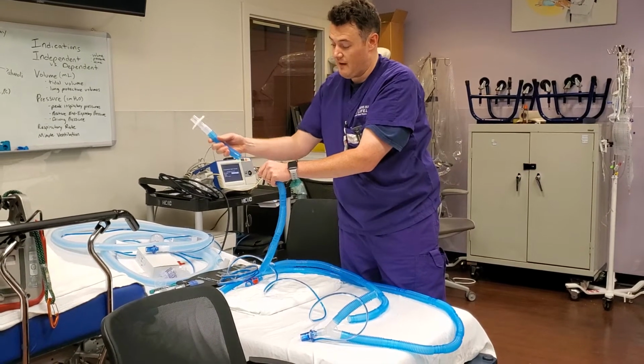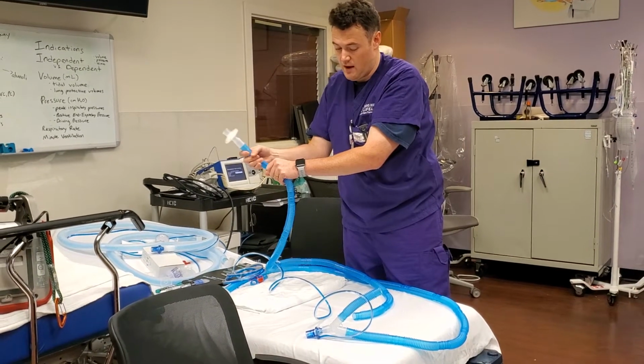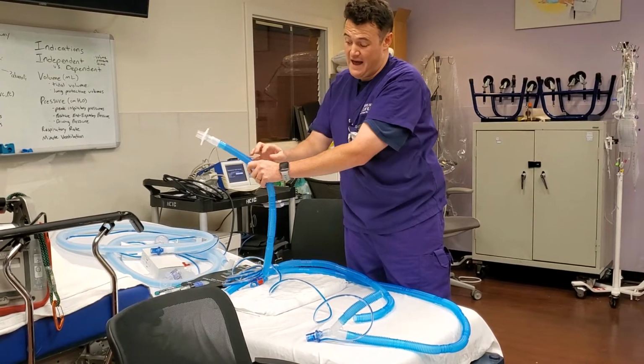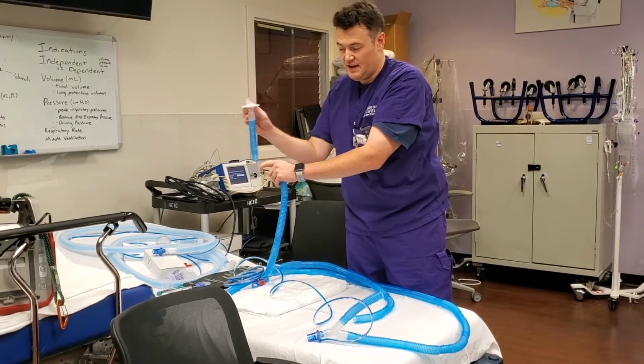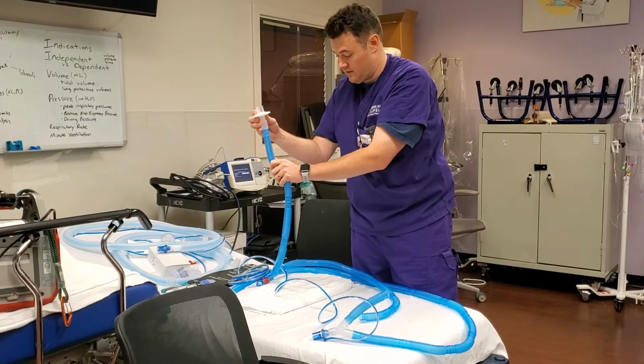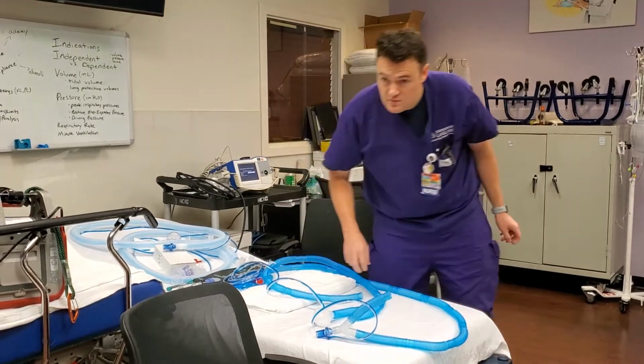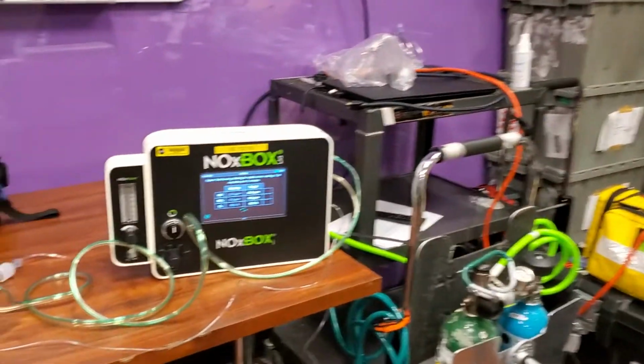When we do put that in line, we obviously want to make sure that our arrow is facing the right way, and then we don't want any filters past the injector module itself. It's fine to obviously have your filters on the ventilator themselves. So once we get this completed here with our test, I'll show you the full setup on the ventilator.